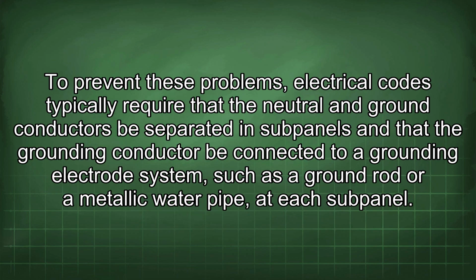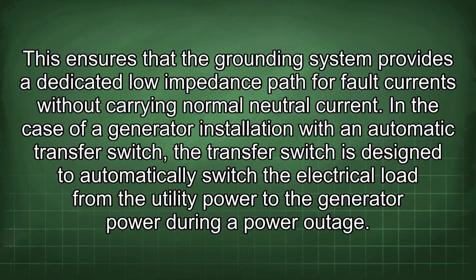To prevent these problems, electrical codes typically require that the neutral and ground conductors be separated in subpanels and that the grounding conductor be connected to a grounding electrode system, such as a ground rod or a metallic water pipe, at each subpanel. This ensures that the grounding system provides a dedicated low impedance path for fault currents without carrying normal neutral current.